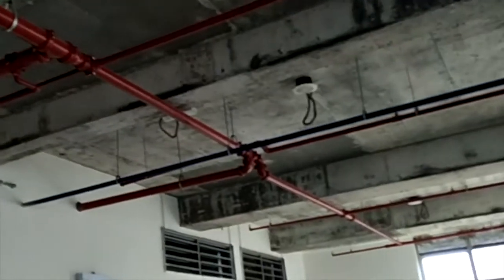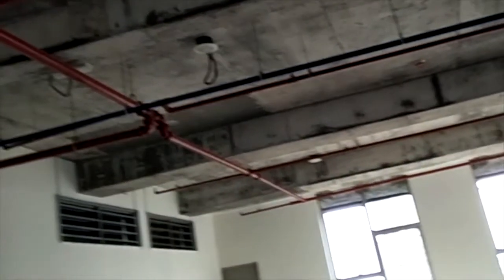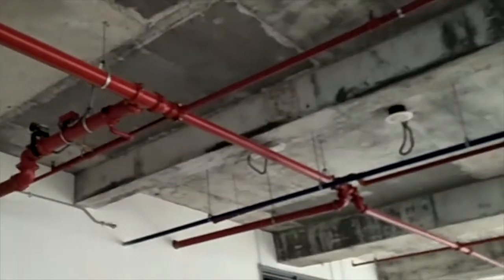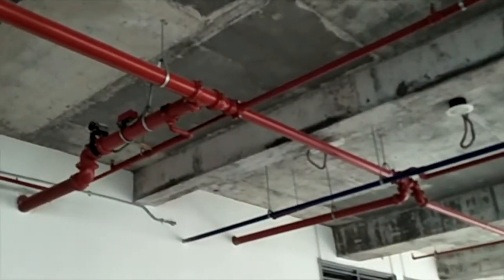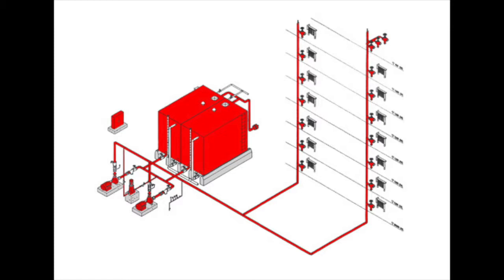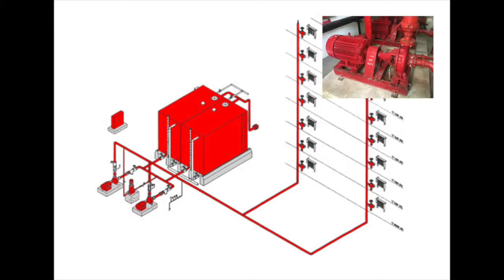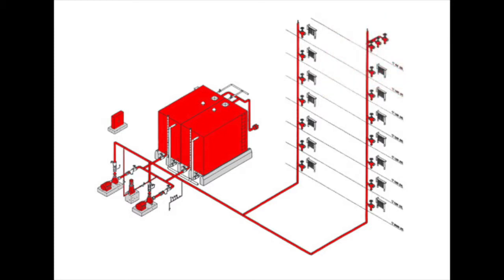In Wisma Mustafa Kamal, the wet pipe sprinkler system is utilized, where it constantly contains water in them so it can act as a quick response to fire. Wet risers are used to supply water within buildings for firefighting purposes and are permanently charged with water.